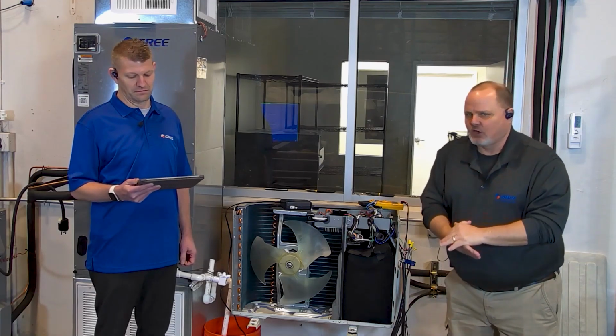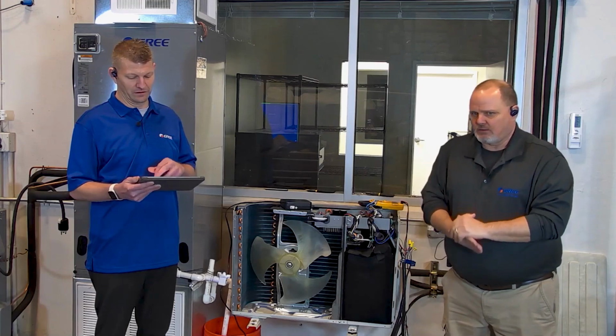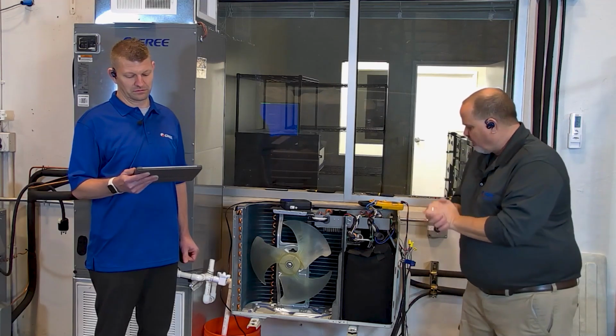You need to pull a vacuum, break it with nitrogen, pull a vacuum, break it with nitrogen, pull a vacuum, break it with nitrogen. The more times you do that, the faster you're going to get that thing down to 500 microns. If it's cold outside, you're only exacerbating the problem. It is going to take even longer for you to get that refrigerant out of there and to get a deep evacuation. I've even done it myself, and I've told guys this before, and you'll see it on this machine I got right in front of me.